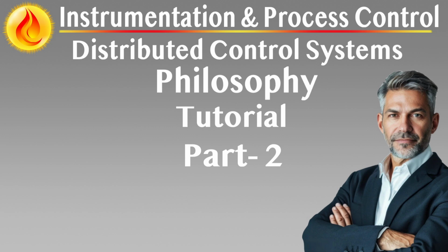Overrides and reset logic. Controlled maintenance overrides. Overrides are restricted to SIL-verified maintenance override switches (MOS), and are only available under multi-tier approval through the DCS HMI under strict role-based security. Each override is logged and visually indicated with backlit status displays. Inputs tied to critical trip functions, e.g., manual ESDs, cannot be overridden.